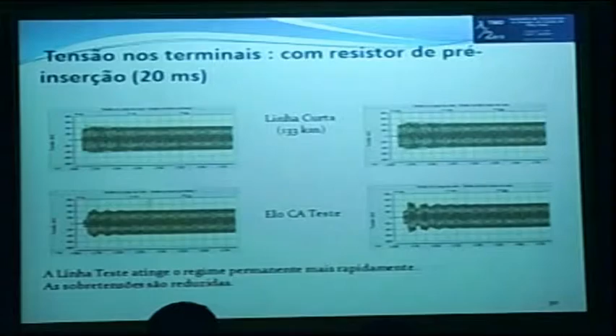This would be the voltages in the short line and the half-wavelength line using the pre-insertion circuit breaker for 20 milliseconds. So now moving on to the conclusions. The higher the short-circuit power in the sending end, the smaller would be the overvoltages throughout the half-wavelength line. We're going to work with one generator, but this idea is not so strong yet, so the overvoltage is not so severe, even talking about one generator.